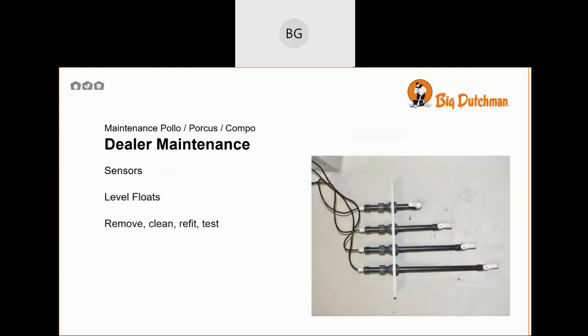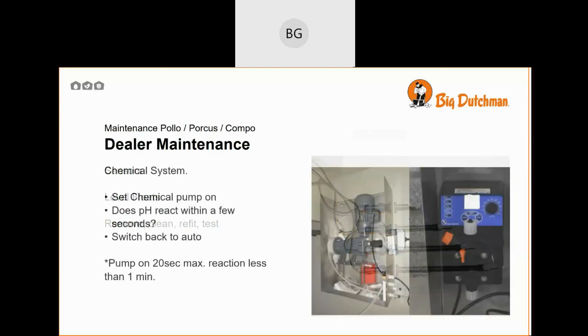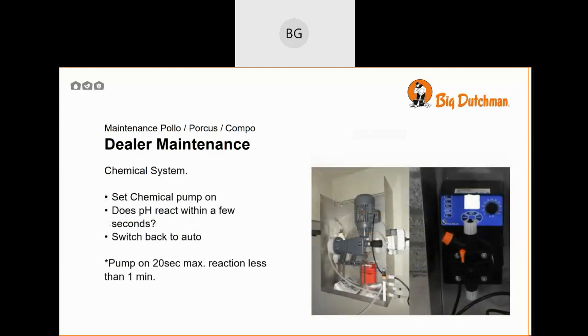Remove, clean, refit and test the level floats. For each level float, there will be a different operation. For the chemical system, set the chemical pump on. Does the pH react within a few seconds? And then switch the chemical pump back to automatic. As a note, don't have the pump on manually more than 20 seconds. The reaction should be within less than a minute.